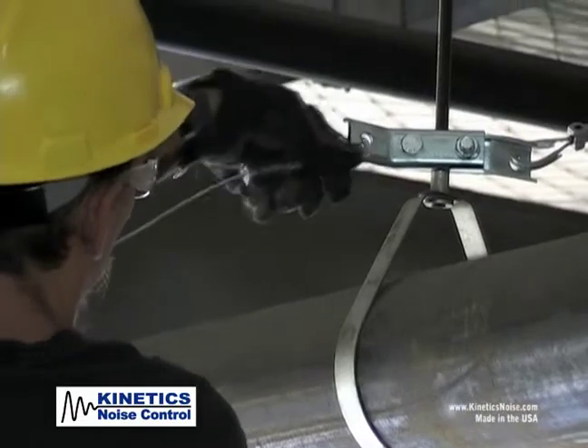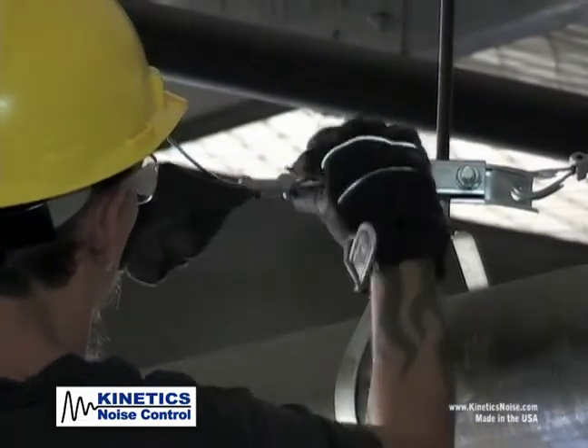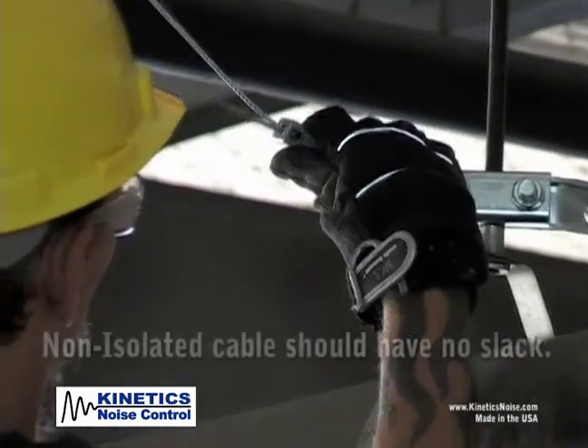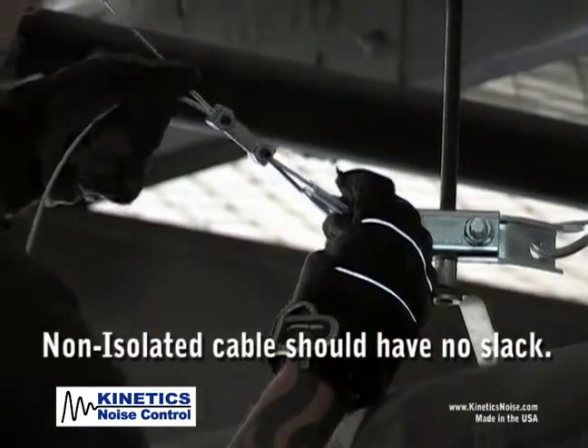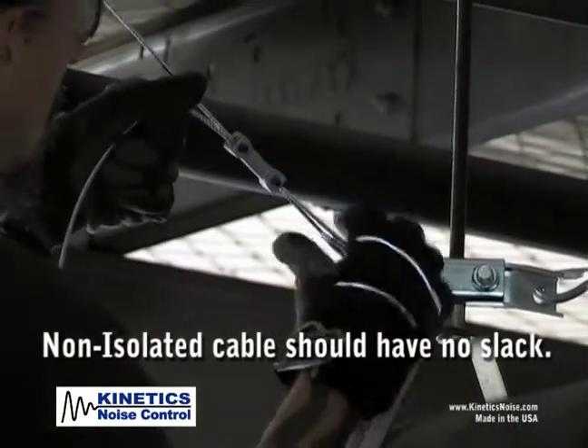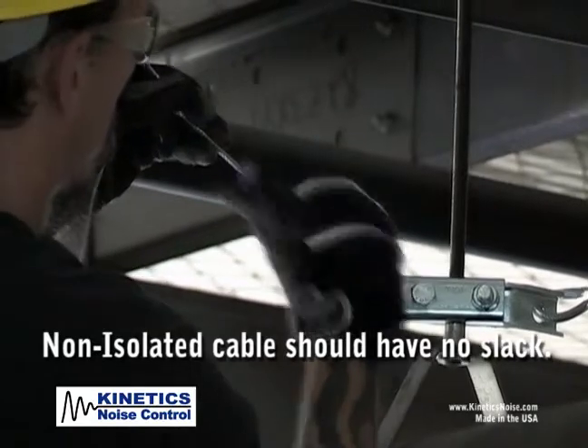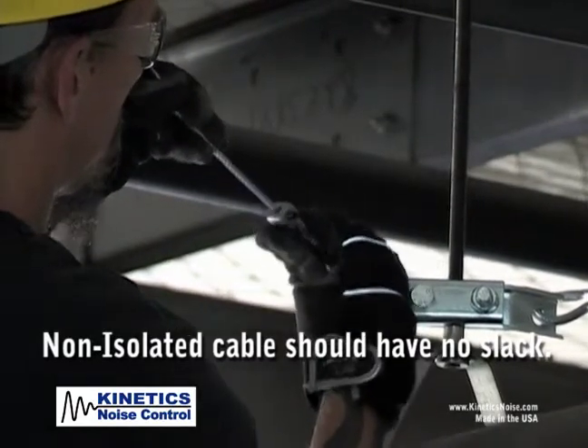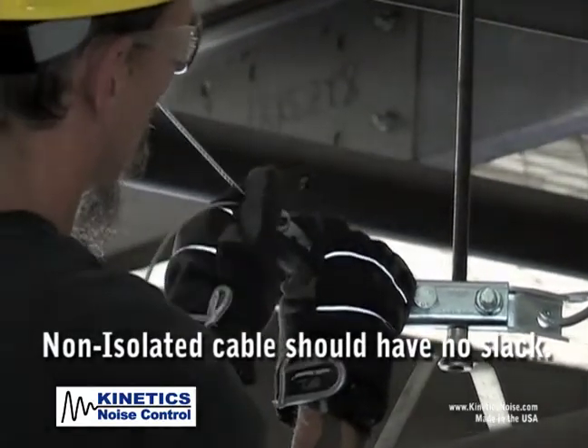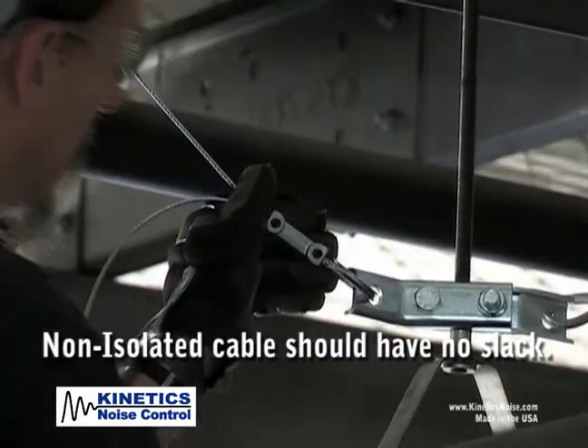Bring the QuakeLoc snug against the thimble and remove the slack from the cable. If isolated, the cable should be left slightly loose to prevent transfer of vibrations into the structure. Slightly loose can be defined as having approximately 1/8 to 1/4 inch of visible sag in the cable.